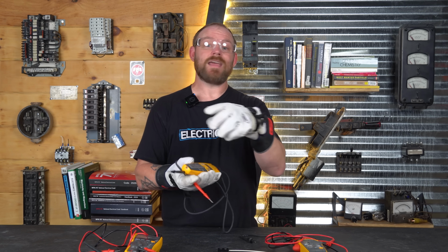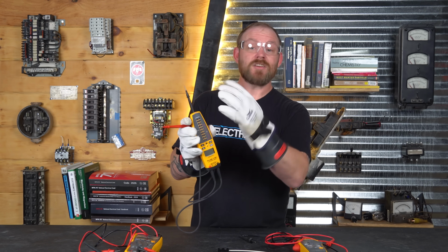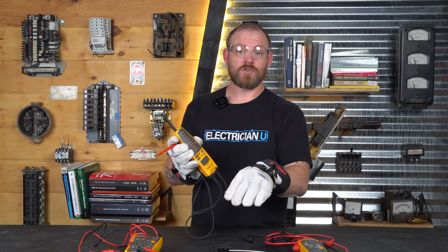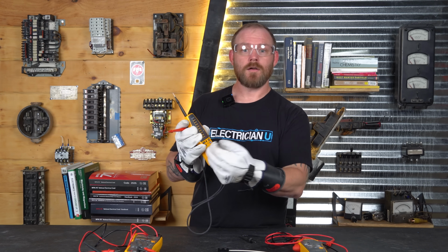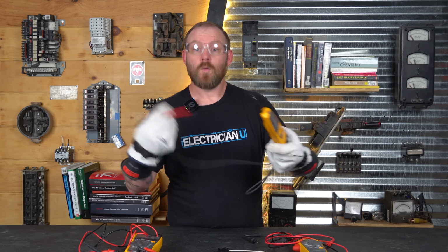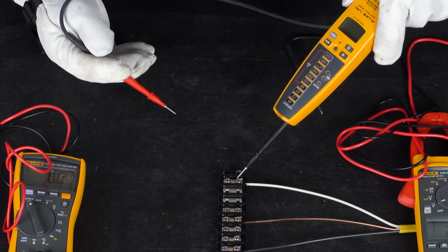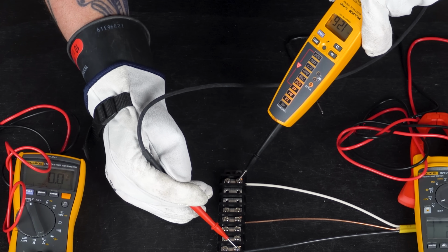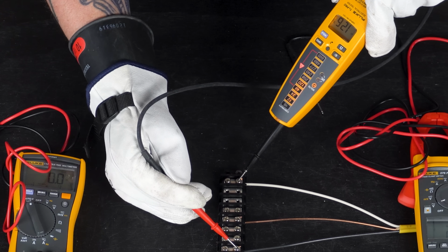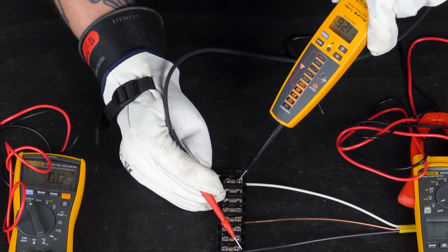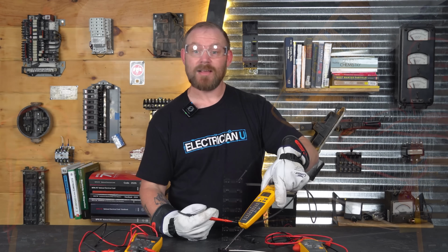And this is a solenoid replacement. There's a very similar thing. It has a digital screen. It still works to detect ghost voltage, and it has 2 different parts of the meter. So if you have a certain threshold of voltage, the screen will light up. You notice there's no power button on here for me to turn anything on. It works based off of if there's a real potential available. So this thing, boom, I know, okay, it's turning on. There's enough voltage to light up that screen to turn it on. Plus it's telling me down here the nominal voltages, it's got up to 120 volts. It's buzzing at me. It's vibrating in my hand.